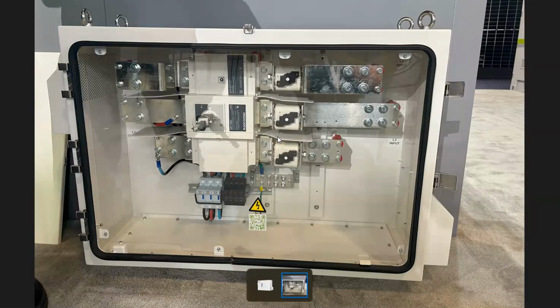And it went through all of the abnormal testing for short circuit, voltage spikes, every kind of abnormal that you would introduce when you're doing product development and going through certification testing. This product was evaluated, and it was found that by testing the product with the inverters, so this kind of combined solution, the self-protection response of the inverters essentially mimicked having individual circuit protection for each inverter, and that it wasn't needed. This was kind of an innovative feature that we came up with and tested and evaluated and got the certification for. So this product has been used for quite a few projects.